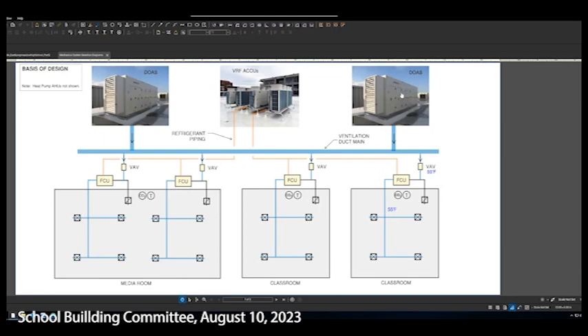There are also rooftop units we call DOAS units, which are basically an energy recovery unit bringing in conditioned outdoor air and distributing it through a ducted system. Each classroom would get a VAV box, which can modulate how much ventilation air goes into the classroom based on the carbon dioxide levels measured there. If the room is lightly occupied, carbon dioxide levels would drop, and the VAV would throttle closed, saving energy by not delivering more ventilation air than is needed.